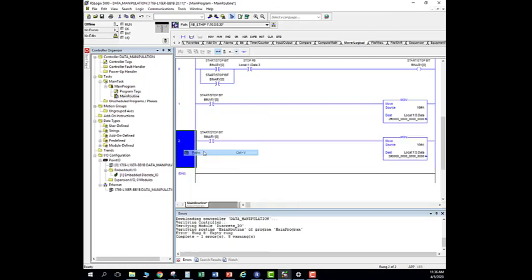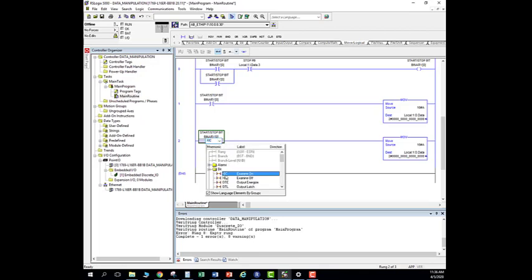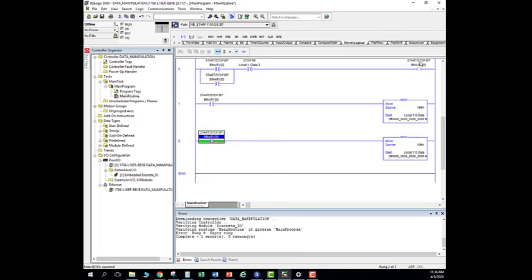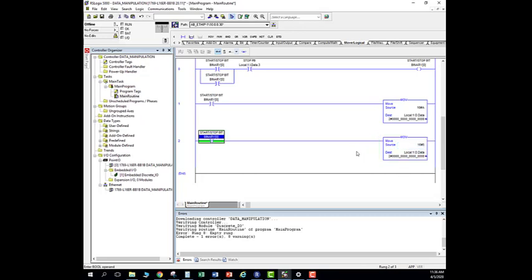Now I'm going to duplicate this — the easiest way to create logic is by copying it. So I'm going to copy it and paste it here. Here I want to make sure it's on the off state, so I'm going to go XIO so when this bit's off it turns this on. In the off state I want to put a 5 in there. As we all know 5 hex is the same as 5 decimal, but I put it in as hex just so we understand that we can create a hex value and it doesn't have to be in A, B, C, D, E, or F form.